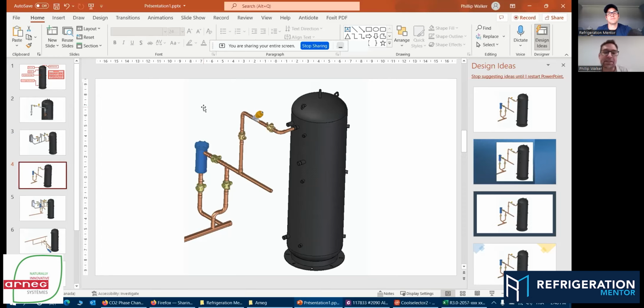Now, what's really interesting about this, do you always need a controlled valve, in the sense of non-mechanical, for a flash tank? I think some of the guys are going to go out there and say, yeah, well, small flash tank drums, like when we go down to 20 kilowatts, this valve isn't driven by a control system. It's a mechanical valve on there. We use a certain type of mechanical valve with a solenoid for emergency reasons, and it's driven as we put our set point, we adjust our pressure setting, and on a small 20 kilowatt system, there is no electronic valve driving that flash. The system's just too small, right?